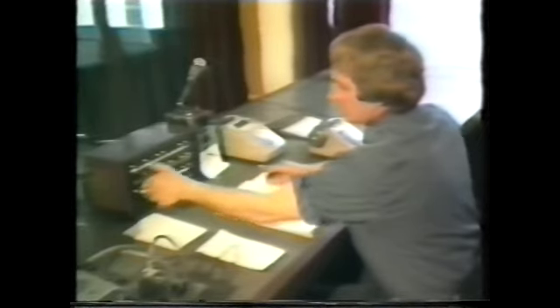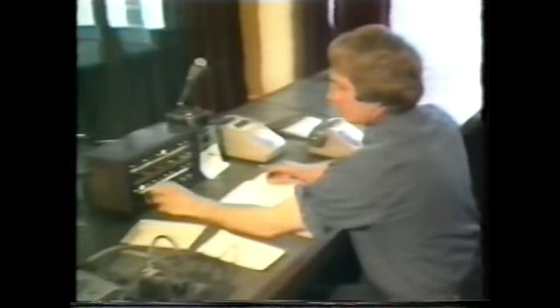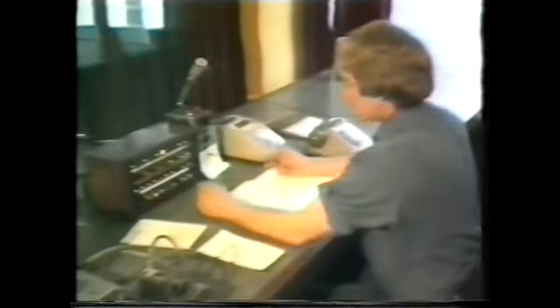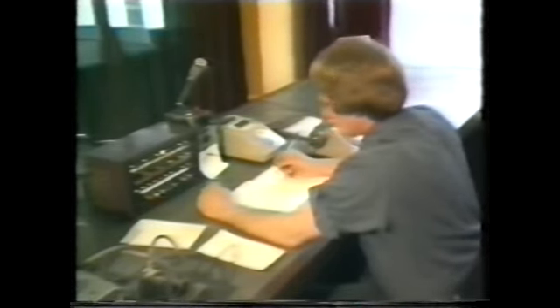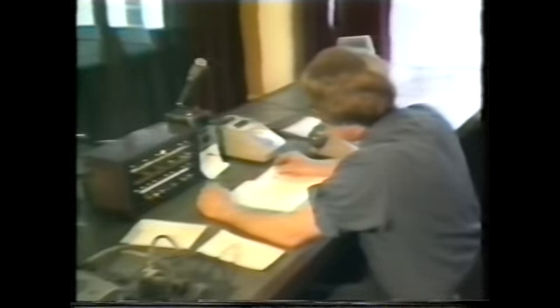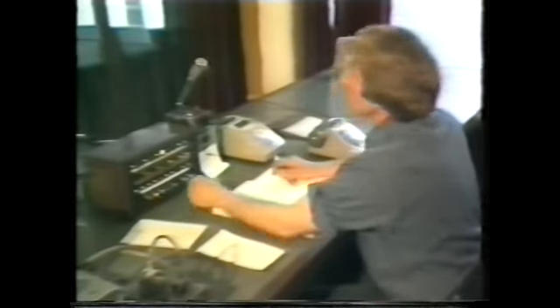After the roll call, the duty man in the watchroom tests the fire call bells and lights. He checks the dispatch lights are working. These are different coloured lights to indicate which fire engine or items of special equipment is needed. In a logbook, he writes the names of the firefighters who are on duty, which fire engines they are riding, and that all safety checks have been carried out and are satisfactory.